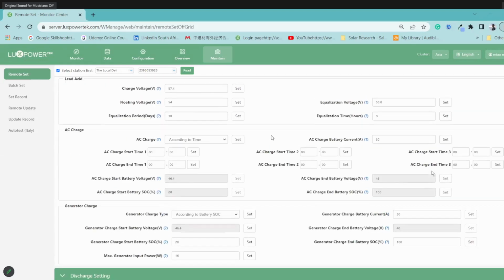AC charge. With AC charge, you have three options: according to time, according to battery voltage specifically for lead acid only, and according to SoC. In most cases, you're probably going to want to use according to time as it works best. So if your client doesn't want to use battery at all, you can also program this, where you leave AC start time at 0000 and just change the end time to 2359.